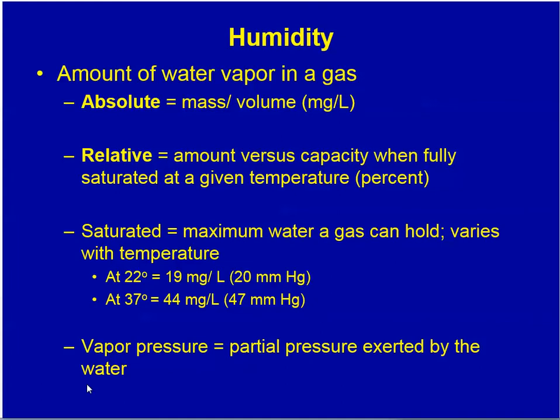Let's turn to the topic of humidity. Humidity is the amount of water vapor in a gas. It can be expressed as absolute humidity — the mass per volume in milligrams of water per liter — or relative humidity, which is the amount of water versus the capacity when fully saturated at a given temperature. Saturation means the gas is holding as much water as it can, and it varies with temperature. At 22 degrees it can hold about 19 milligrams per liter, and at 37 degrees about 44 milligrams per liter. The partial pressure of water vapor at these two temperatures is 20 and 47 mmHg, respectively.